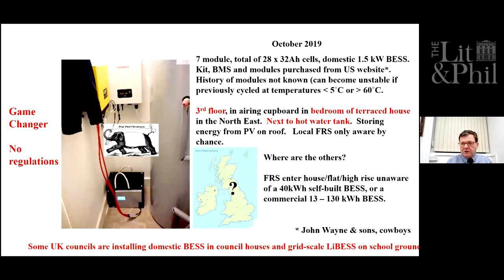This is a system I was called out to by a friend in the fire and rescue services. The homeowner had entirely innocently bought modules online from America, from a company I choose to call John Wayne and Son Cowboys - no history associated with these. If you cycle lithium-ion batteries at temperatures less than 5 degrees C, or at high temperatures, or if you rapid charge them, you can get lithium metal plating, which destabilizes them. This was on the third floor, in the airing cupboard, in the bedroom, next to the hot water tank - and these batteries start to go unstable at around 70 degrees centigrade.